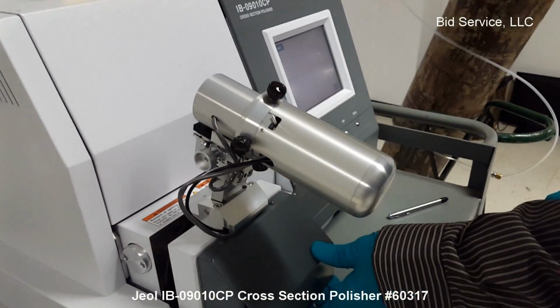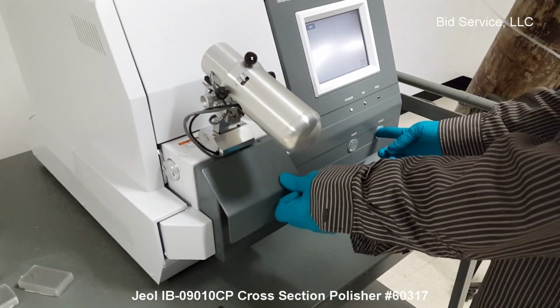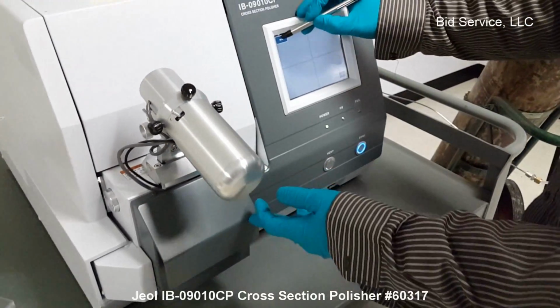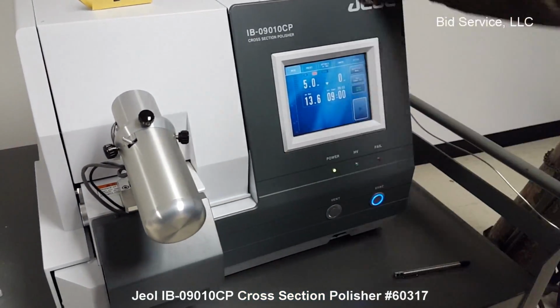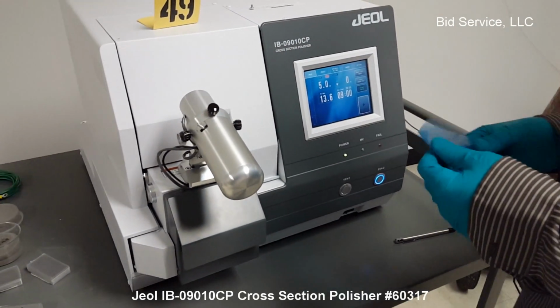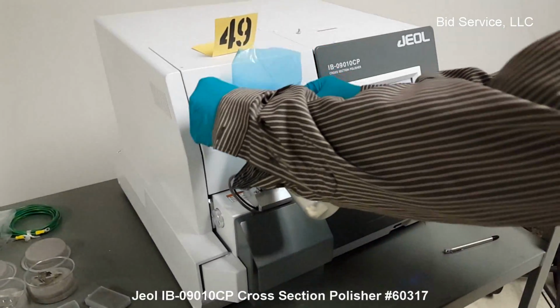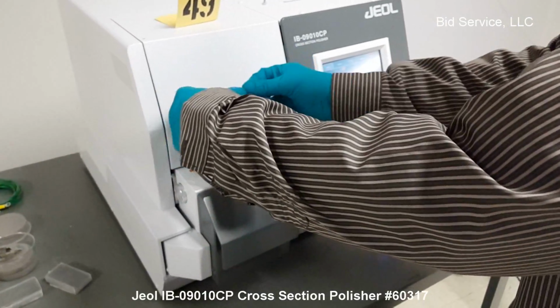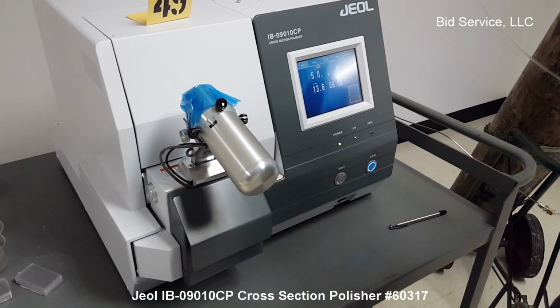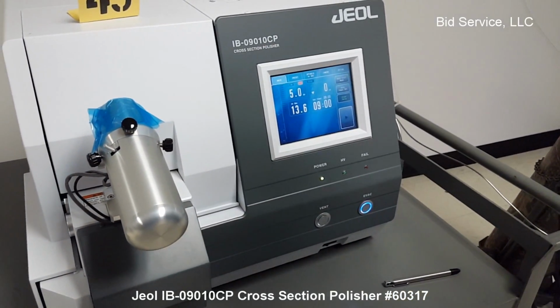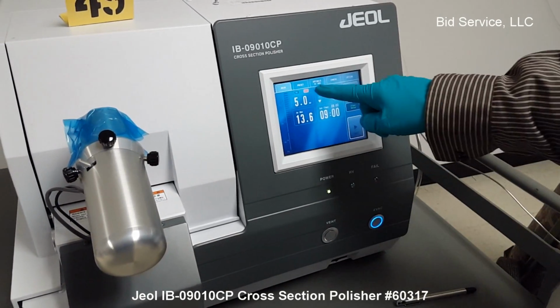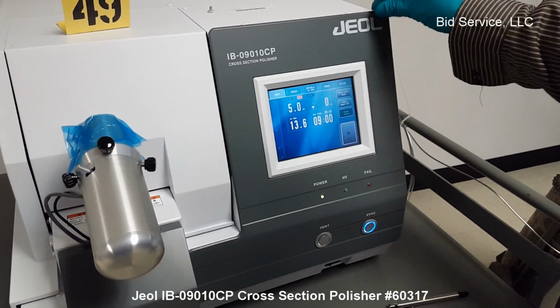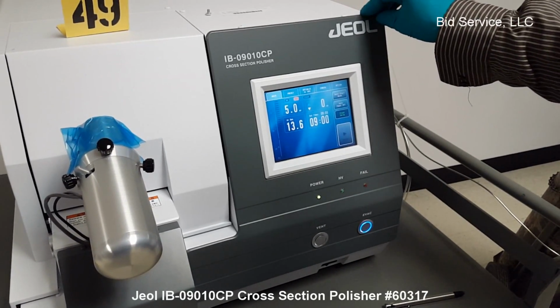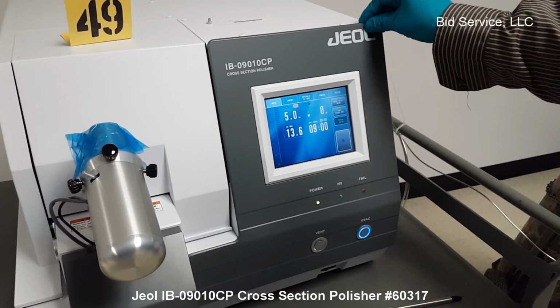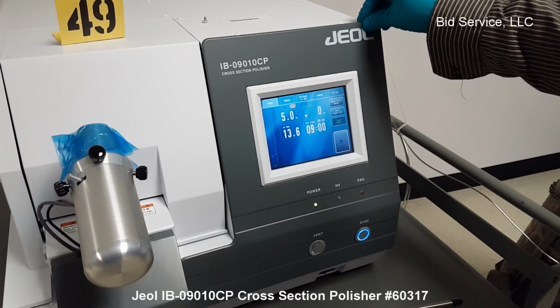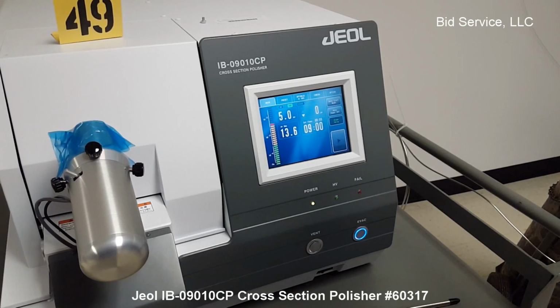So once the sample is loaded and you press the evacuation button and go to the main screen, I'm using a Mylar screen to protect the camera. So the TMP on orange indicates that the turbo is accelerating, the turbo pump. And as soon as it turns green, the penning gauge sensor will energize and start indicating vacuum level.